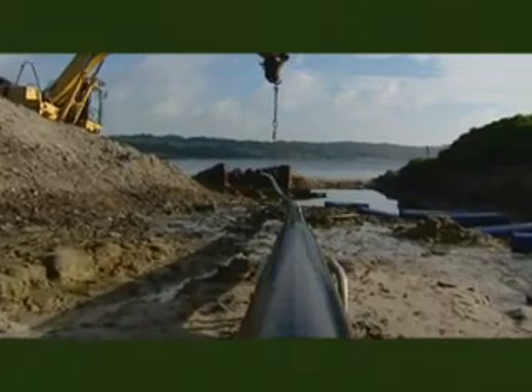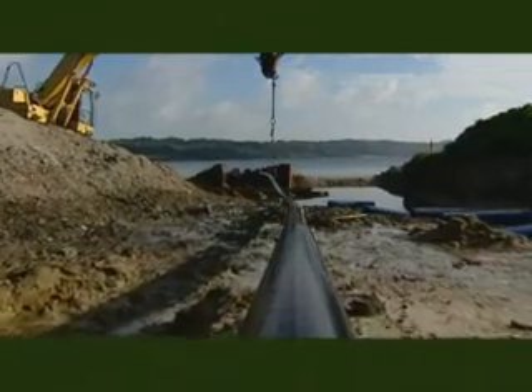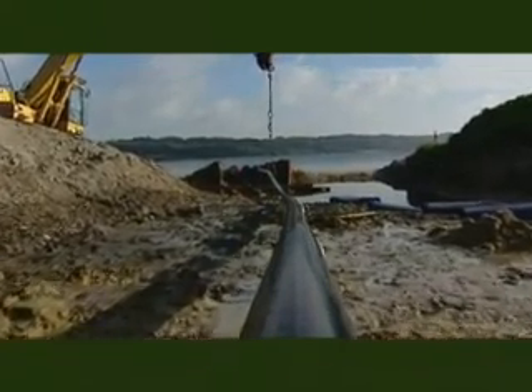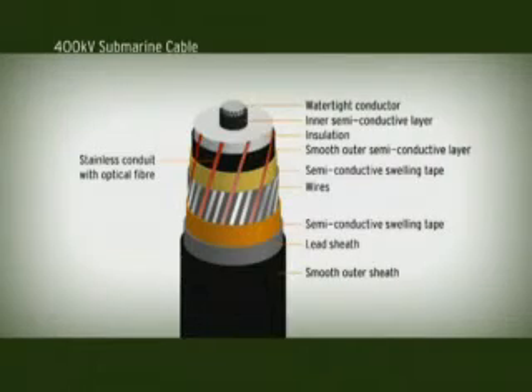The cable running beneath Mariager Fjord distinguishes itself from the land cable in that its water barrier is a lead sheath instead of an aluminium sheath. It was decided to use a lead sheath on this section as the cable pipes are filled with salt water. However, the lead sheath means that the cable is significantly heavier and harder to handle when being pulled through the pipe.